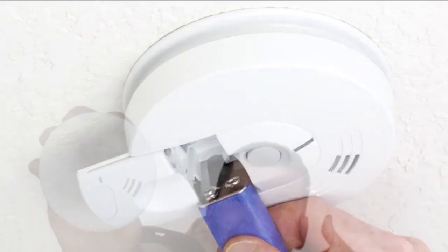The differing strengths of these two types of sensors has led to the creation of detectors that employ both types of systems. This allows for the rapid detection of both small smoldering fires and fast-moving ones. The less common aspirating smoke detectors use a fan to draw in air from the surrounding environment. Next, a system of filtering, sensing, and analyzing the air sample is employed. Depending on the environment needing protection, this system can be as sensitive, some as much as 1,000 times as much as a standard photoelectric or ionization detector, or advanced as the situation requires.